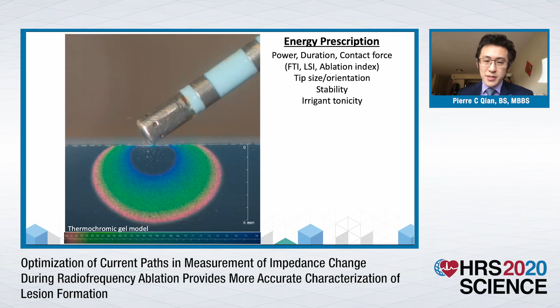Ablation parameters are used to dose RF energy, and calculated indices based on power, duration, and contact force have improved the consistency of lesion quality. However, real-time measures that corroborate tissue heating remain important for titrating energy delivery and avoiding overheating. Among available measurements, circuit impedance drop is readily accessible in real time and can reflect temperatures. This is because tissue heating causes a significant reduction in resistance of about 2% per degree Celsius, as well as reductions in tissue capacitance from disruption of cell membranes. With tissue overheating, air bubble formation can increase impedance and herald steam pops.